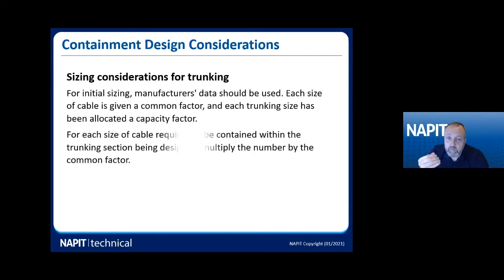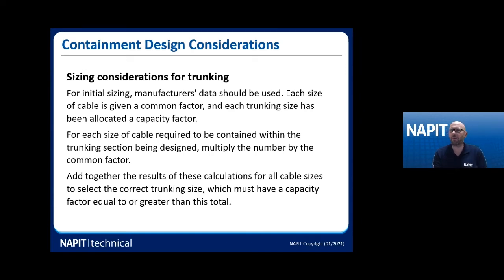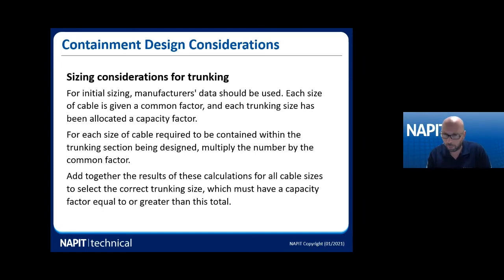For trunking sizing, the best thing is to use manufacturer's data. Each size of cable is given a common factor, and each trunking size has a capacity factor. For each cable size required to be contained, you multiply the number of cables by the common factor, add it all together, and then select the trunking size which has a capacity factor equal to or greater than that total.